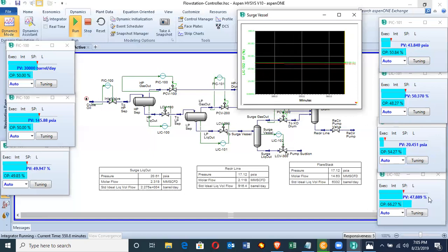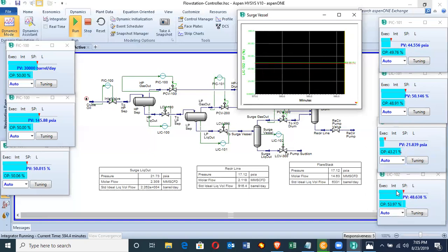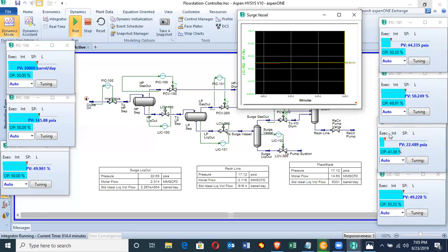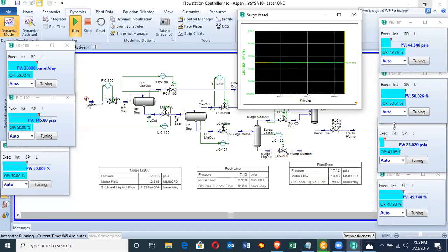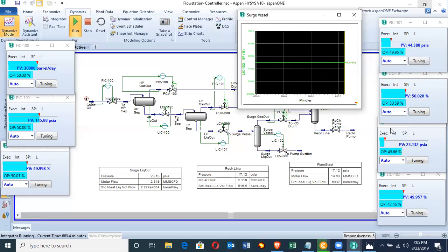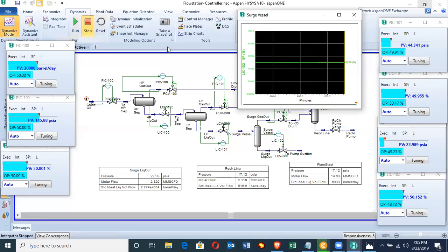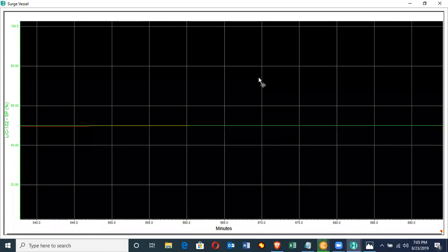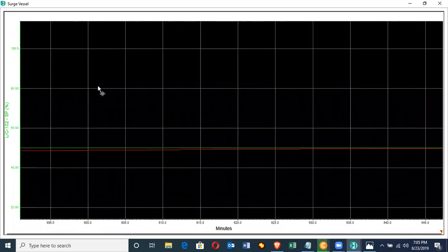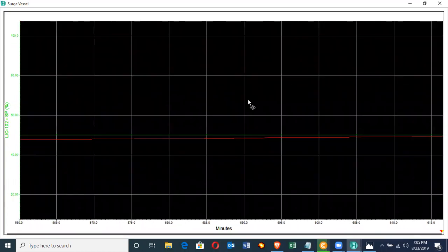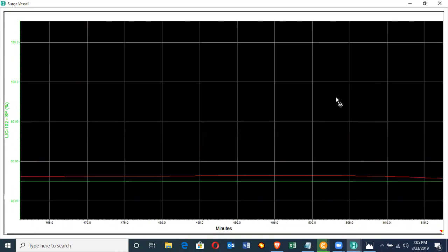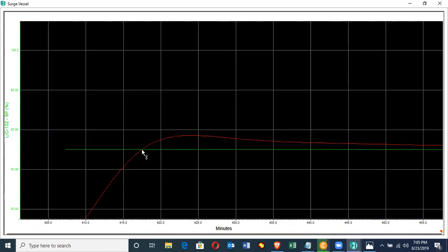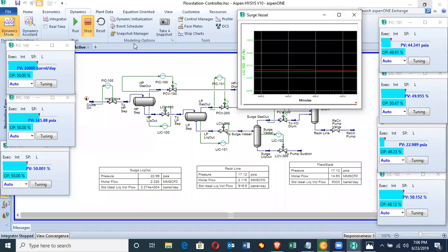See how it's trying to stabilize. There's the level control indicator controller for the surge vessel, there's the pressure indicator controller for the surge vessel controlling the pressure control valve. Now it's normalized. Check when it first got to 50% and check the time. The time is 417 minutes, 417 minutes to fill this vessel.